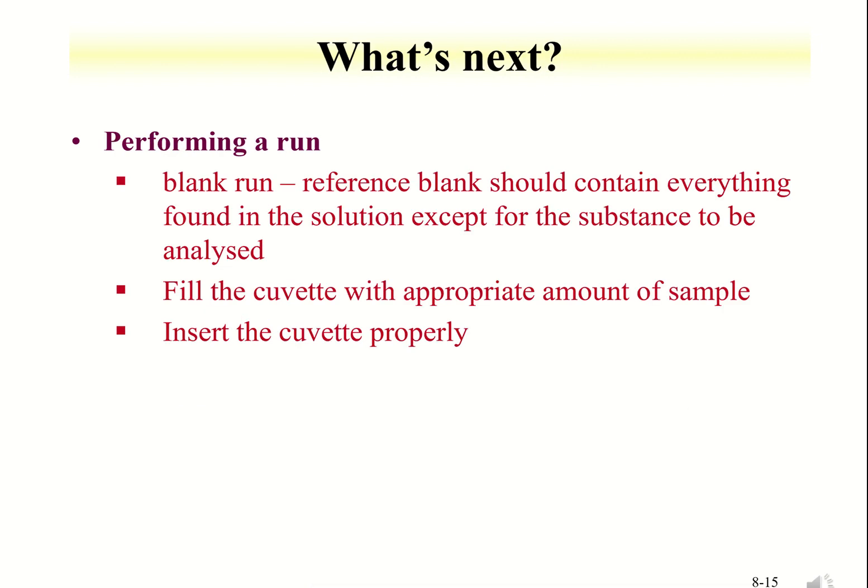To operate a UV spectrometer, we should first perform a blank run. A blank run is done with a cuvette filled with distilled water or solvent which is used to dissolve the sample. This is to ensure that all possible background noise that can contribute to the absorbance is eliminated prior to sample run. To perform a blank run, a clean and dry cuvette is filled with the solvent to three quarters of the cuvette and inserted into a slot with the clear side of the cuvette facing the light path.